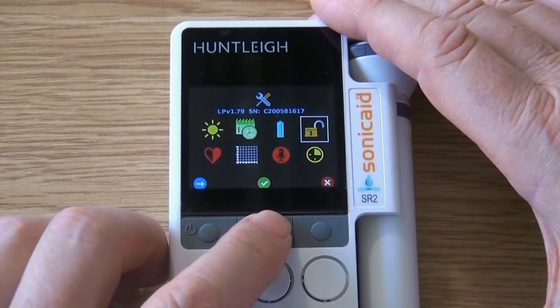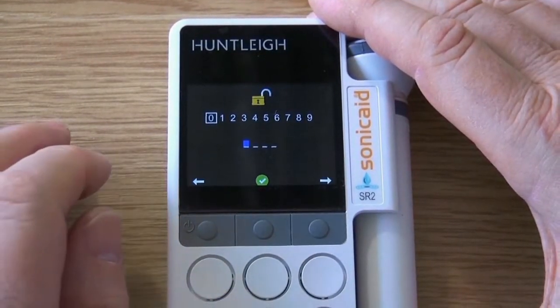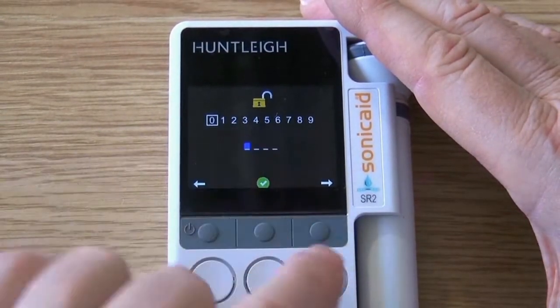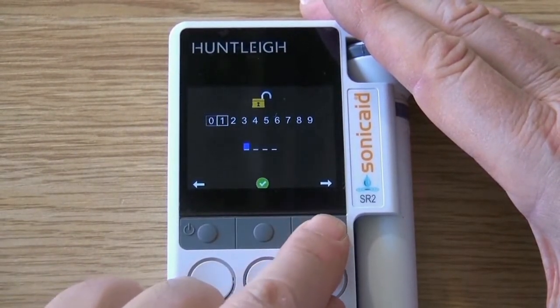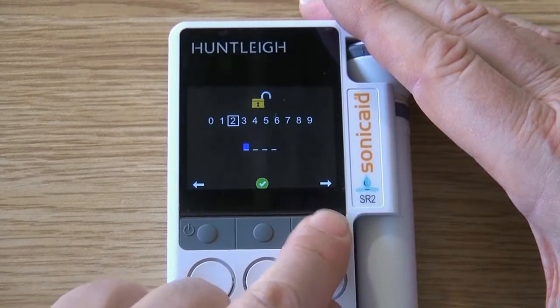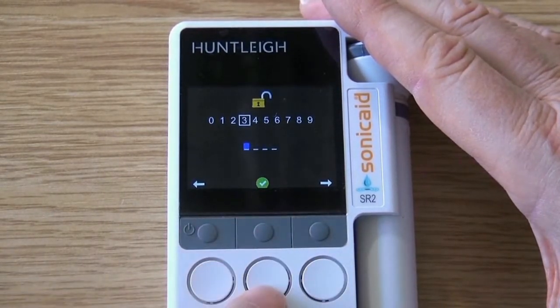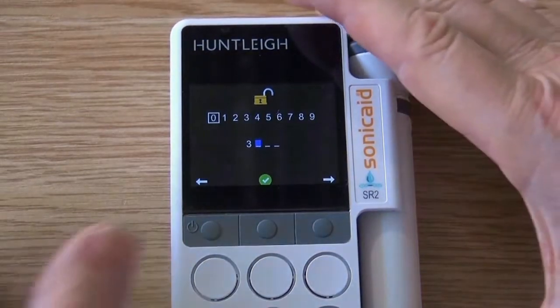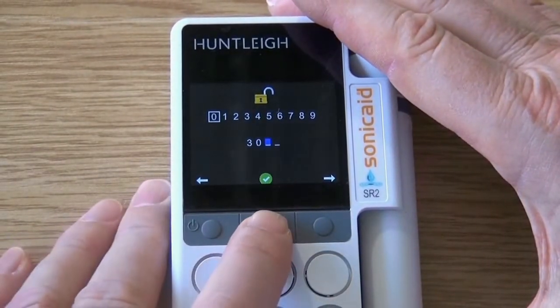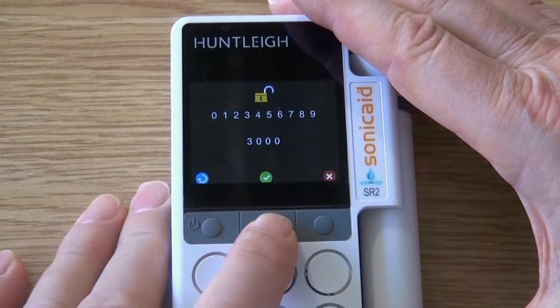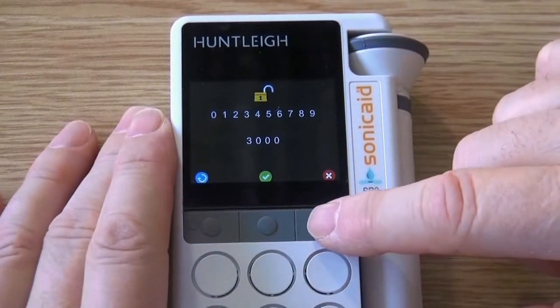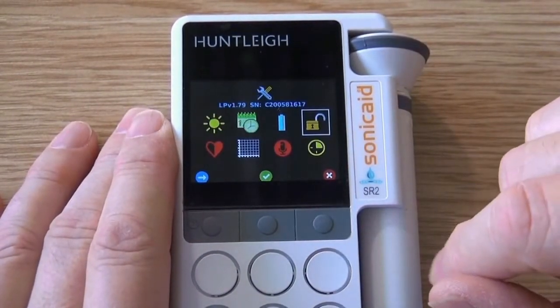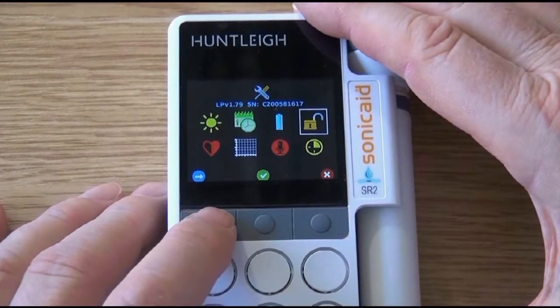With the pin lock icon highlighted, press the middle button. Use the left and right buttons to select the desired numbers. If the pin is to be accepted, press the green tick. If you do not want to create a pin code, press the red cross. Creating a code locks the saved database on the unit. To unlock the database, enter the correct pin code and press the green tick.